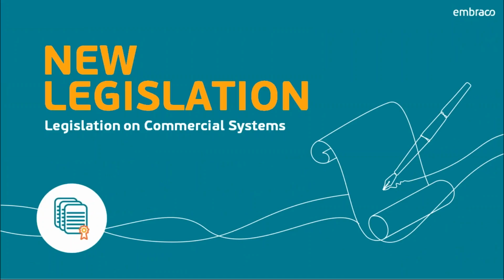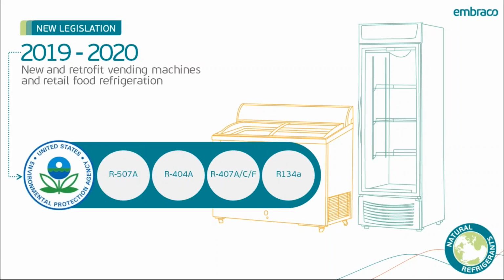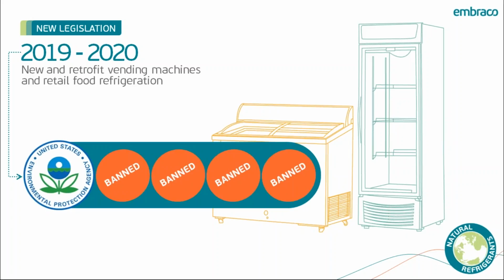So, new legislation on commercial systems that's right around the corner. Starting as soon as 2019-2020, for new and retrofit vending machines and retail food refrigeration, the EPA is going to ban the current refrigerants that we're using in this equipment: the 507A, 404A, all the 407s, A, C, and F, and 134A. All of these are going to be banned.